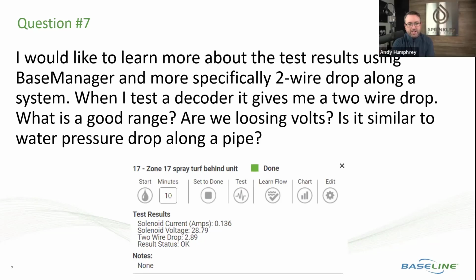Yeah. I did check with tech support because I didn't know the details of this. What they told me is under 4 is sort of acceptable. Between 4 and 6 starts to be questionable. And above 6, you start to get communication failures. So you may do a test all and you may get sporadic messages like can't communicate with device. And it could be a different device every time you test because there's so much voltage loss that we're losing the communication signal out there. And things like nicked wire, bad splices and such over time can cause that voltage drop to increase.